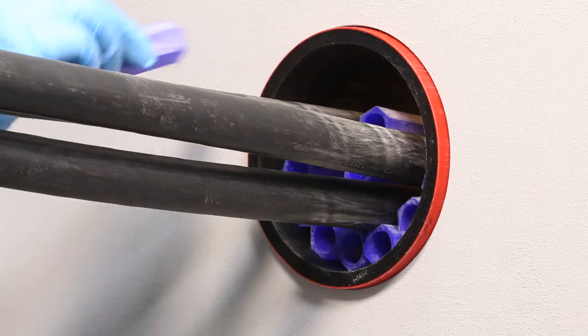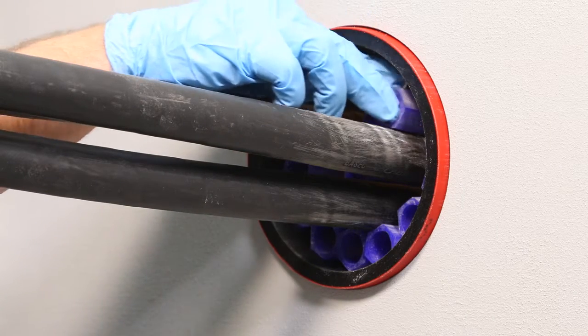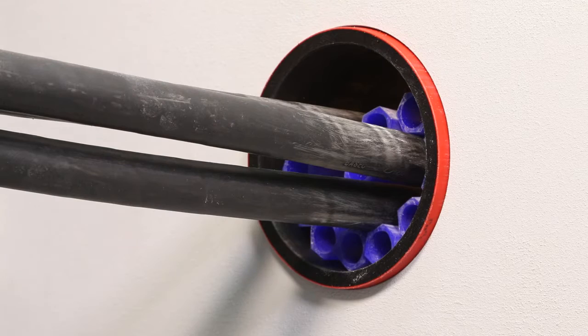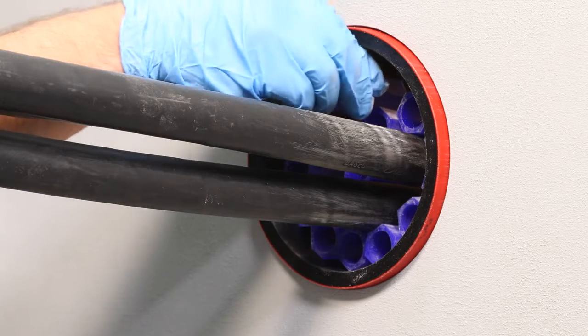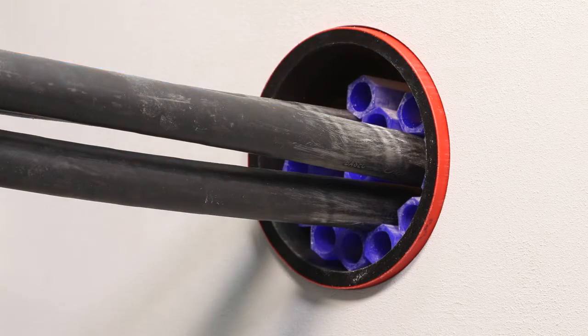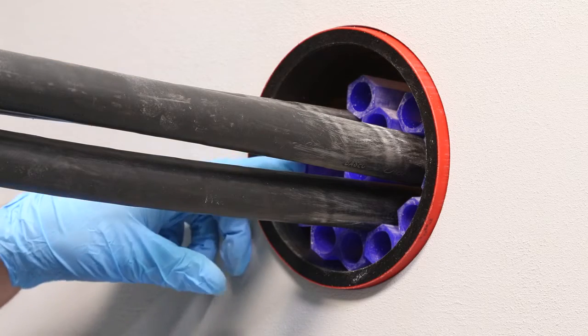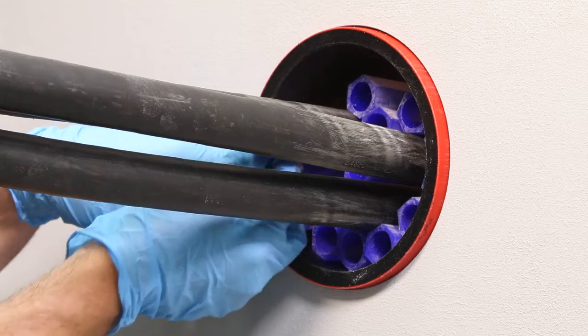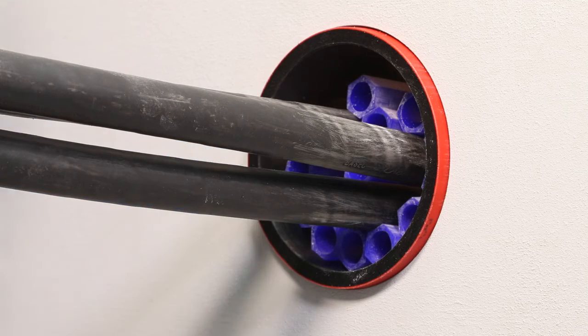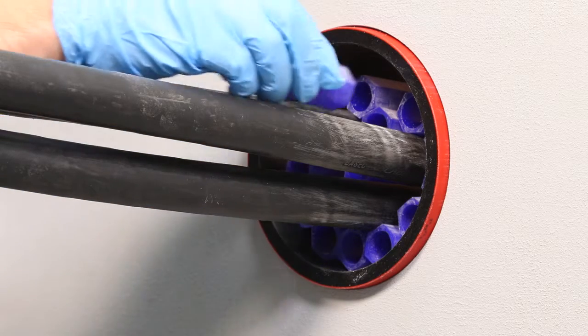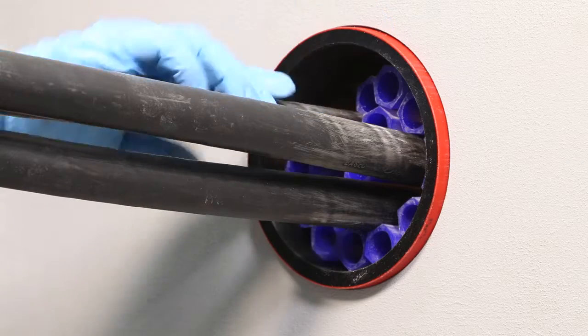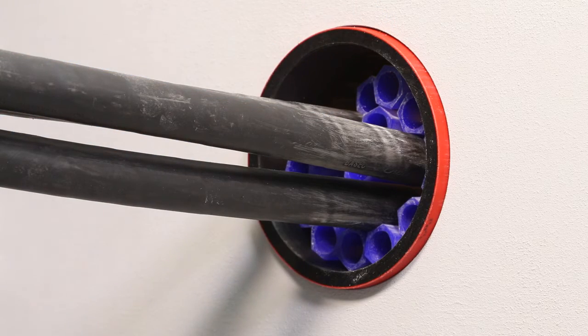A neat installation is with the flat sides of the hexagonal tubes coming together cleanly. The tubes can also be cut and wrapped around the cable if required. The tubes may also be nested one inside the other. Ensure the tubes are packed in tight by using as many tubes as possible. There are smaller tubes in the kit to fill out the last small spaces.